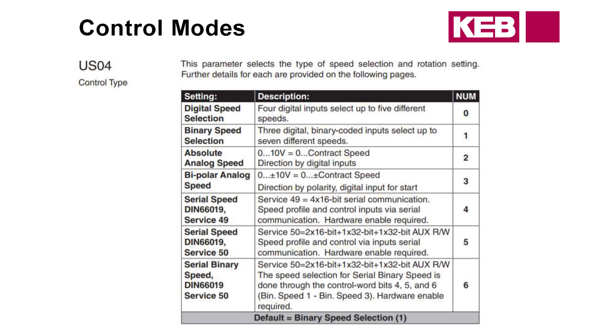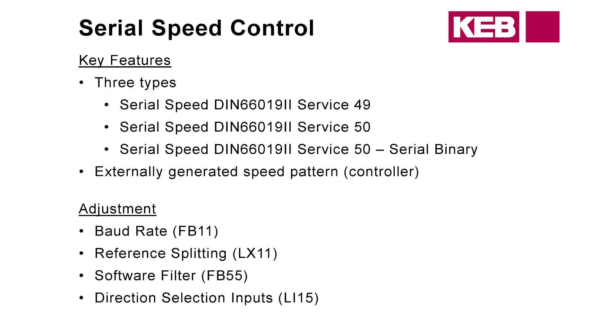We also have a hybrid between binary and serial called serial binary. For serial speed control, the controller is going to be in charge of the profile. I will caveat that with SmartRise — it's a little bit different. What they do is actually send over the final speed to the drive, and it's up to the drive to ramp up to that final contract speed.